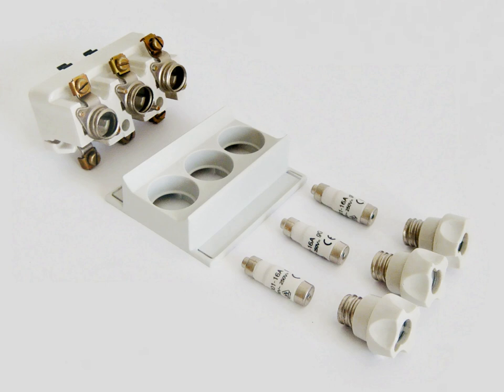For the NEOZED fuses, there are also fuse bases with integrated disconnecting switches. Changing fuses with the circuit off increases the safety of the user. With new versions of these load disconnecting switches, the fuse cartridges are no longer screwed, but are held by spring clips. Traditional DIAZED fuse holders are made as a conducting metal envelope covered with non-conducting porcelain cover.